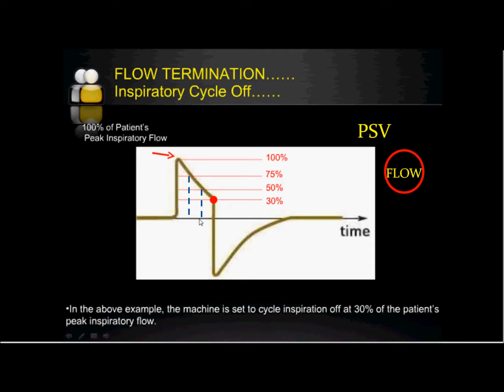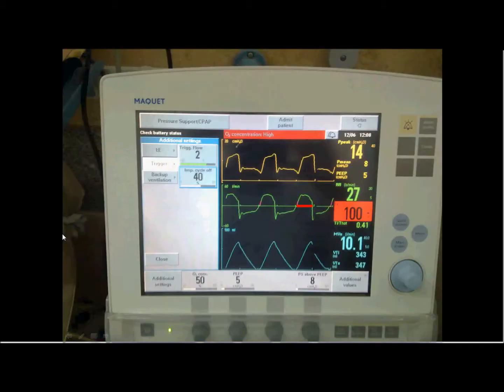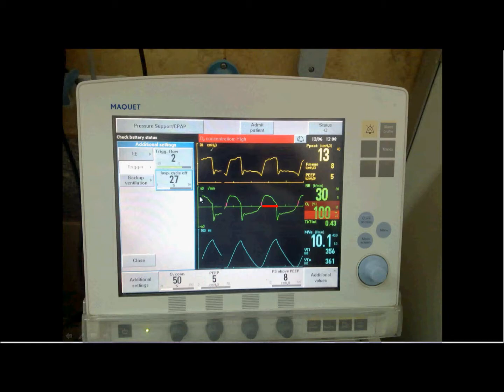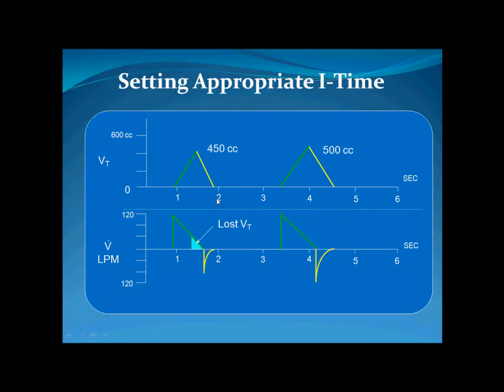By adjusting expiratory sensitivity, you adjust the inspiratory time of the machine, which in turn determines the tidal volume. For example, if the cycle is at 40 percent of peak flow, then changing it to 27 percent means you are increasing the inspiratory time, and accordingly the tidal volume should increase. When you increase the sensitivity threshold to a lower flow level, you are prolonging the inspiratory time, which increases the tidal volume. It is a simple relationship.